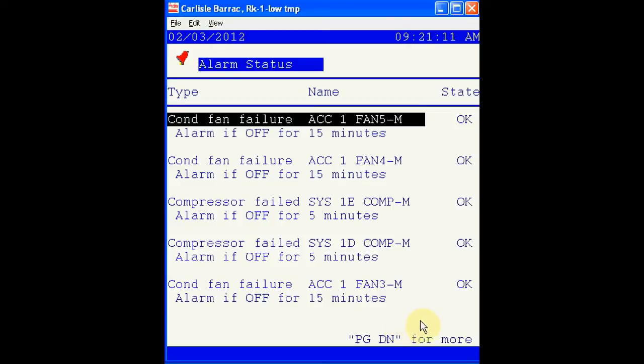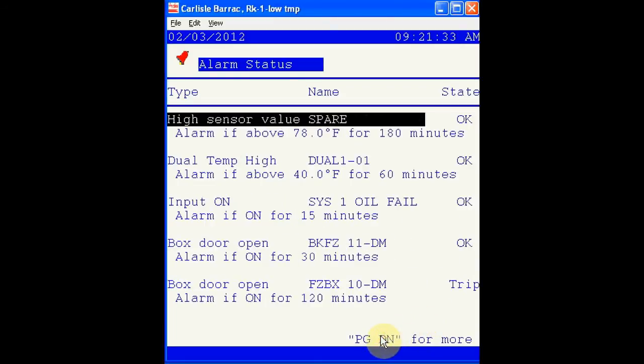A useful tool is using the alarm status screen to check for any alarms that may be counting down, indicating a problem that could exist. Here, each alarm configured in the controller will be displayed. If there are no pending actions, the state will read OK. You can page down to see all the alarms. This indicates that the box door for this evaporator is actually open and the alarm has tripped. This particular alarm is set to log only and will only be viewed in the active alarm screen.